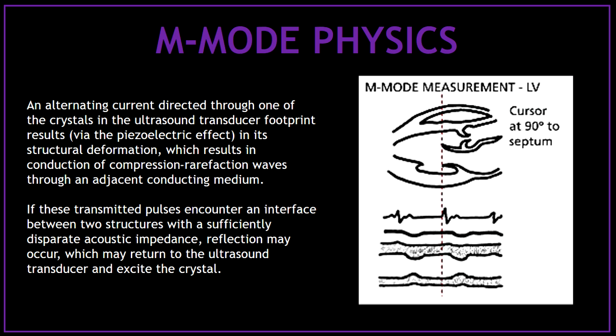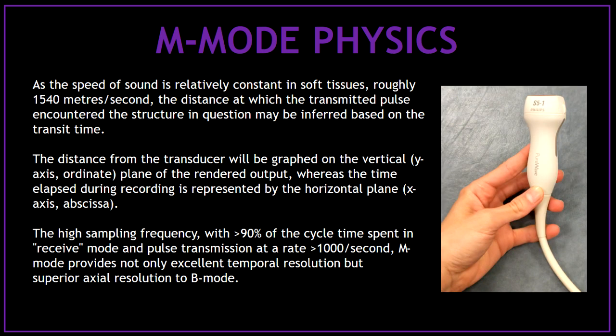An alternating current directed through one of the crystals in the ultrasound transducer footprint results in its structural deformation, which results in conduction of compression-rarefaction waves through an adjacent conducting medium. If these transmitted pulses encounter an interface between two structures, reflection may occur. As the speed of sound is relatively constant in soft tissues — roughly 1,540 meters per second — the distance at which the transmitted pulse encounters the structure in question may be inferred based on the transit time. The distance from the transducer is graphed on the vertical plane, whereas the time elapsed during recording is represented by the horizontal plane.